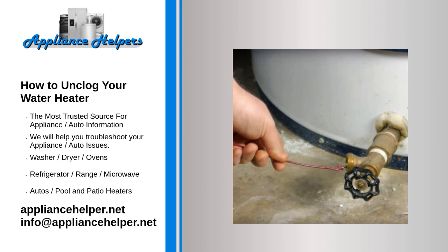Back flushing. You'll need a washer-fill hose for this trick, as it has female connections on both ends. Attach one end to the drain valve and the other to your washtub or another nearby faucet. Then, open the drain valve and turn on the water. The water pressure will push its way up through the sediment, dislodging the clog. After a couple of minutes, shut off the water, close the valve, and remove the hose to begin regular drainage.